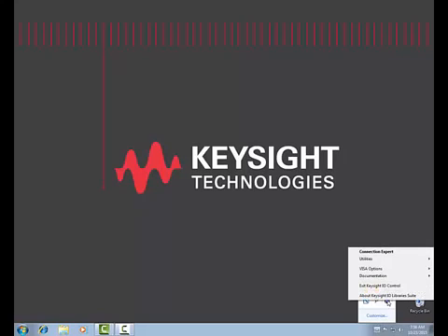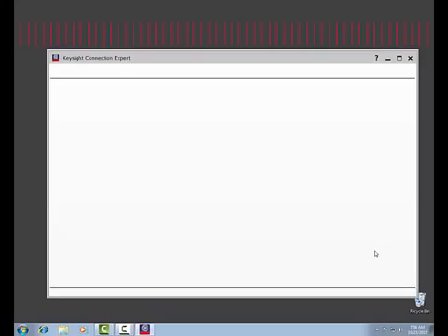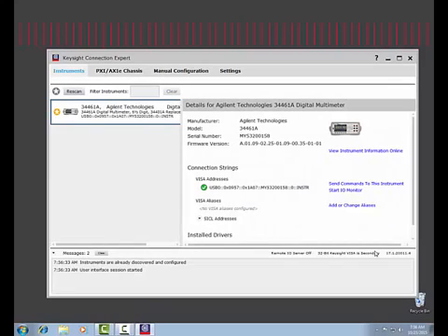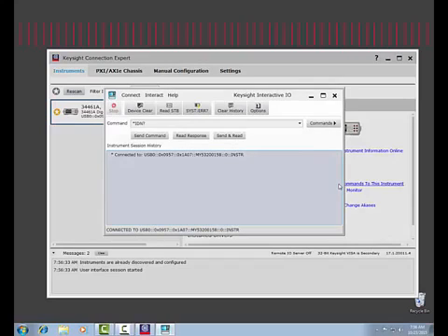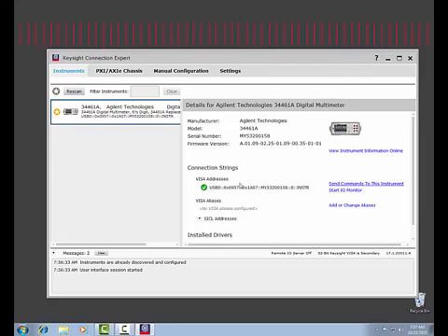Now let's launch the Keysight IO Library Suite's Connection Expert. Now, this is optional if you're using the IO Library Suite instead of NI VISA. Here you see the same instrument. We have our VISA address here. And we can also send commands to the instrument from here. We have the same command pre-populated. If we go ahead and do a send and read, we verify communication, just as we did before. Check for errors. And there's our VISA address once again.